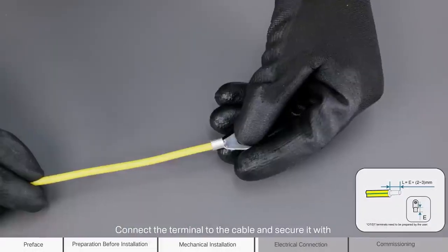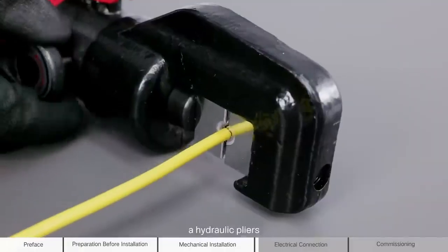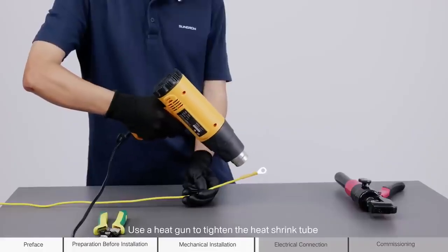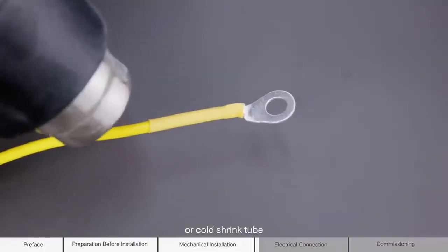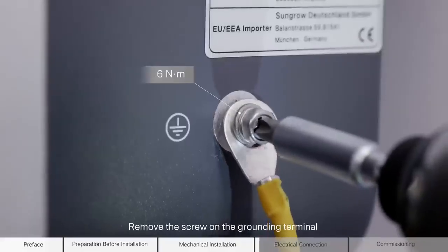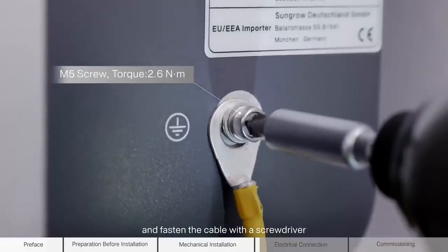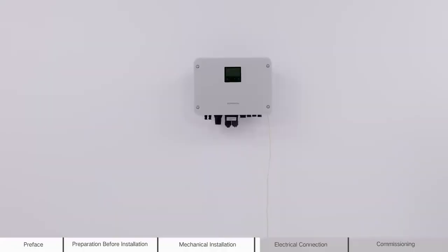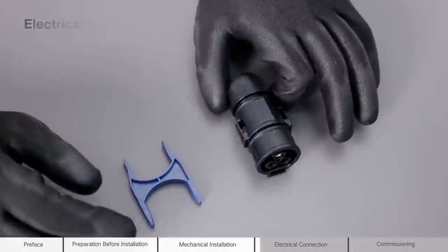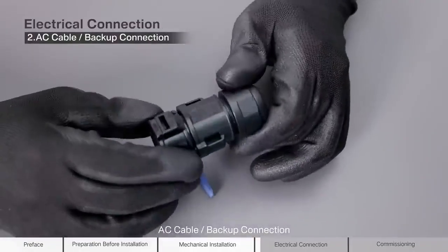Connect the terminal to the cable and secure it with a hydraulic pliers. Use a heat gun to tighten the heat shrink tube or cold shrink tube. Remove the screw on the grounding terminal and fasten the cable with a screwdriver. 2. AC cable or backup connection.